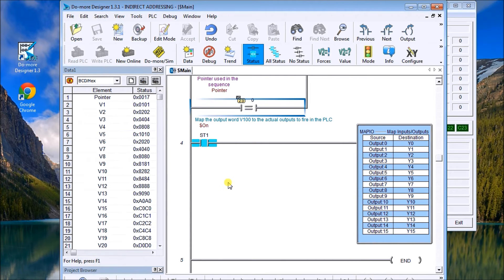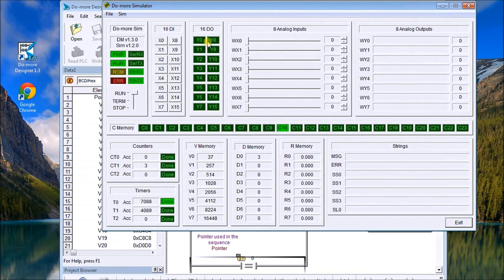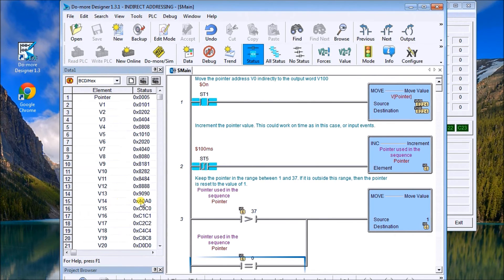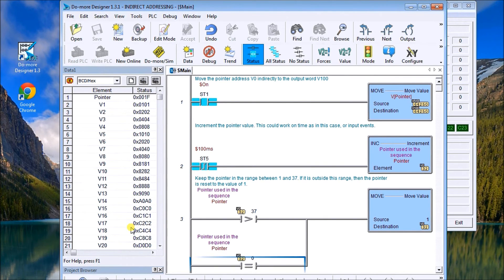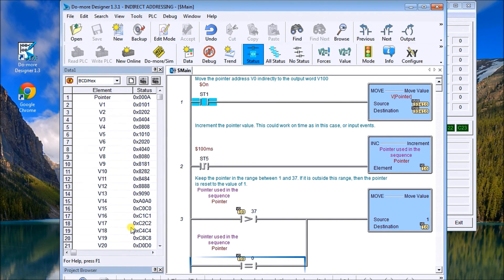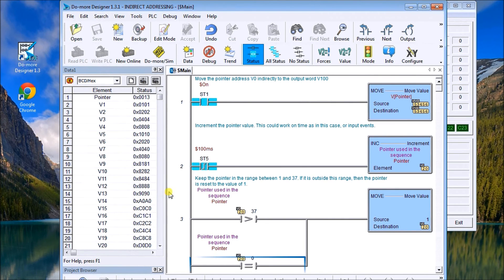So you see four rungs will allow you to do sequencing just about anything. The beauty of this is when you actually come back to change the sequence, instead of changing all of this code, you're only changing data points within the structure here. So it becomes very straightforward, very easy to do. And right now what we've done is set outputs. You could also do the same thing by using compares on predetermined tables and moving the outputs then. And if you go to the website you'll see examples of all of these. The notes are in the links below. Thanks for watching and happy programming.